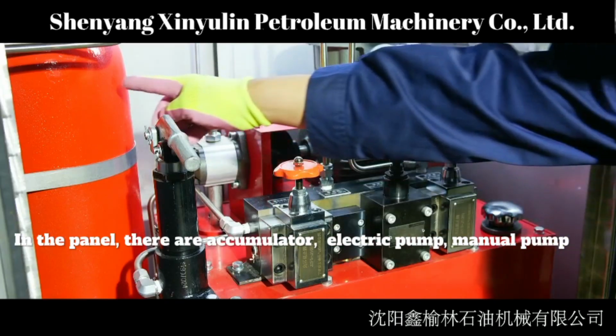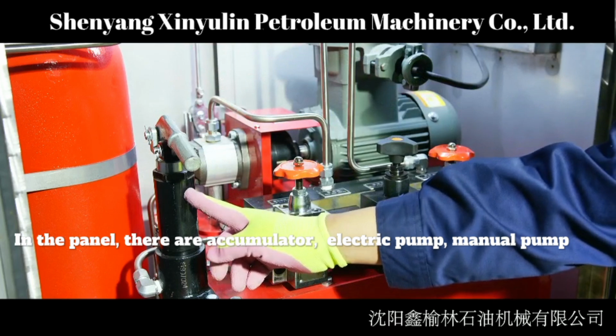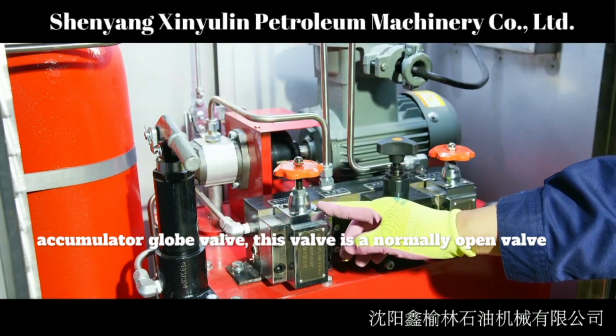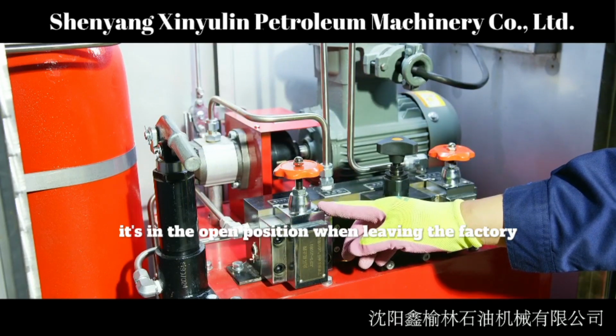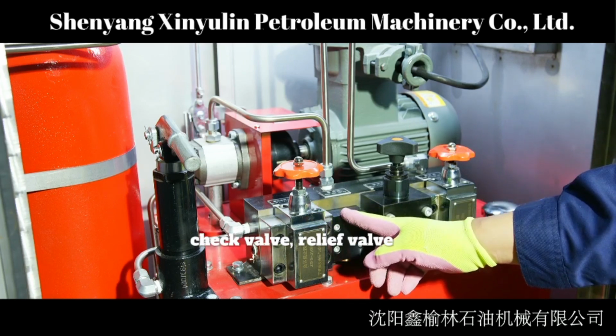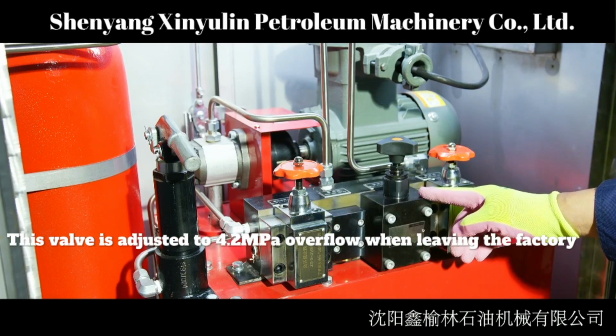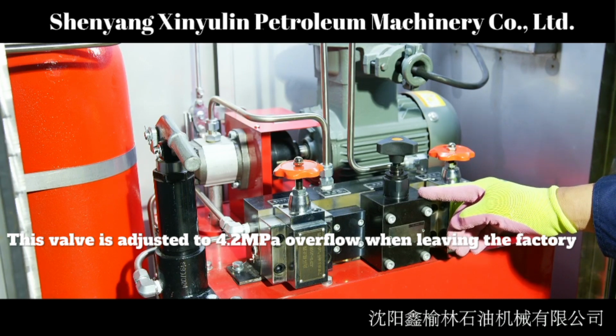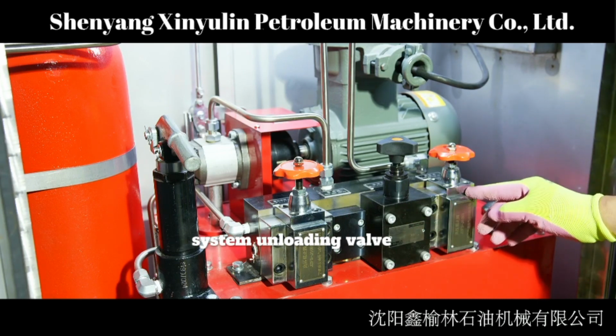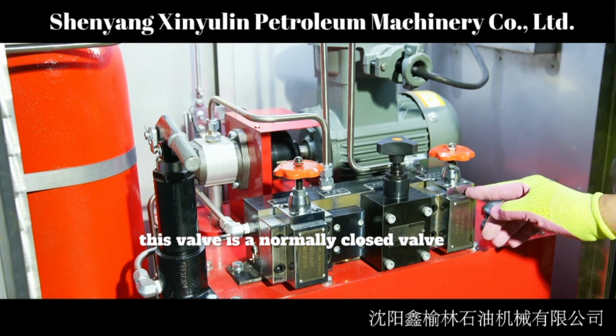In the panel, there are accumulator, electric pump, manual pump. Accumulator globe valve. This valve is a normally open valve, in the open position when leaving the factory. Check valve, relief valve. This valve is adjusted to 4.2 MPa overflow when leaving the factory. System unloading valve. This valve is a normally closed valve. It is in the closed position when leaving the factory.